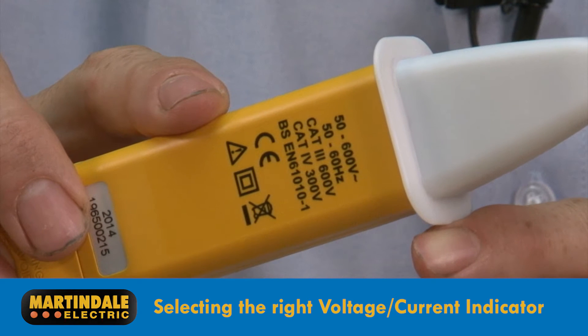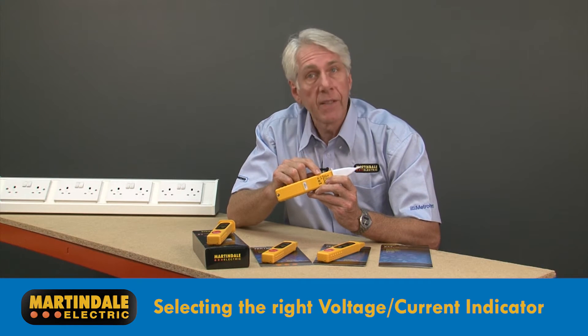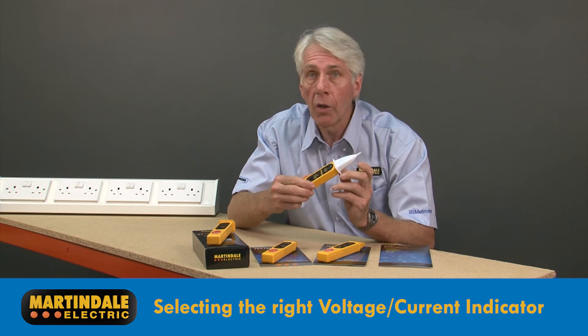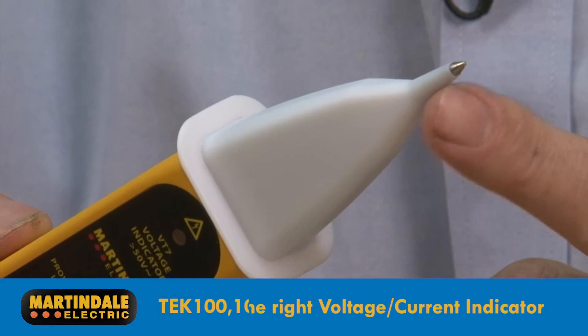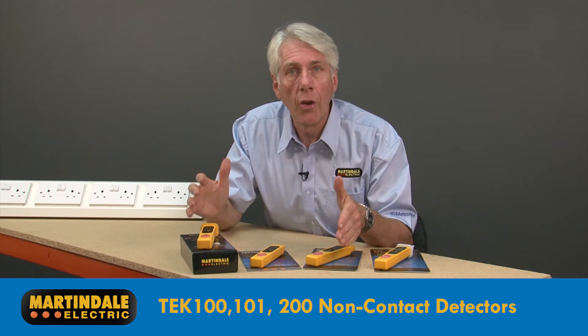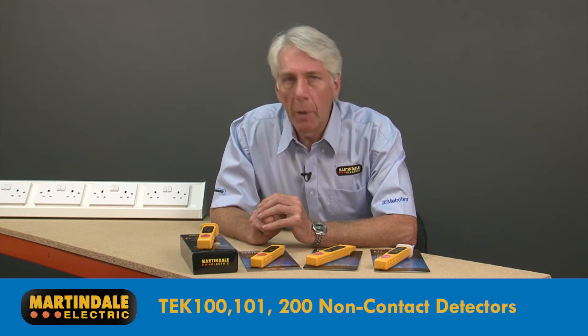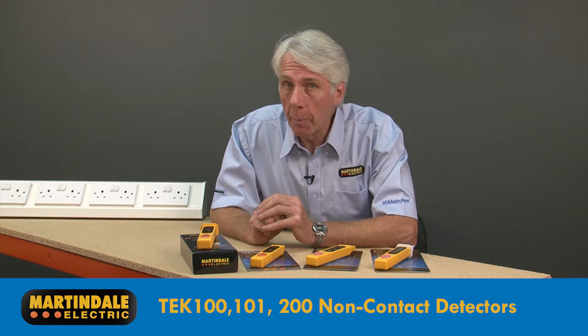This is printed on each device with further information in the user guide. For some applications, a single pole contact indicator like the VT7 may be the best solution. The TEK100, 101 and 200 are non-contact detectors with built-in proving capability, but it is worth mentioning that these should not be used as part of a safe isolation procedure.